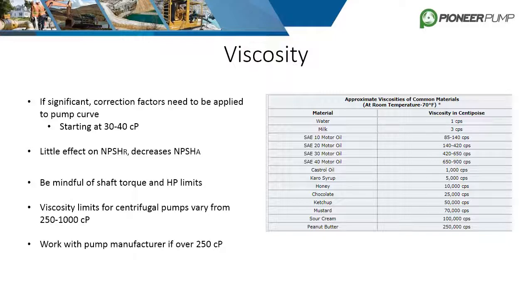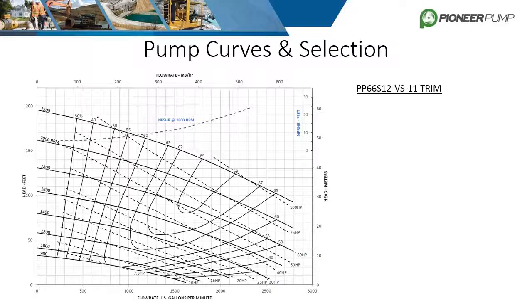It is recommended to work with the pump manufacturer if the fluid is over 250 centipoise. The curve shown is a standard variable speed curve for the Pioneer Prime 66S12, trimmed to 11 inches. There are many lines and figures displayed on the curve, and they are all very important to understand.